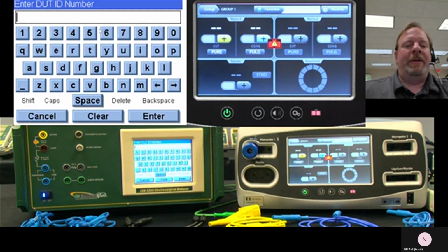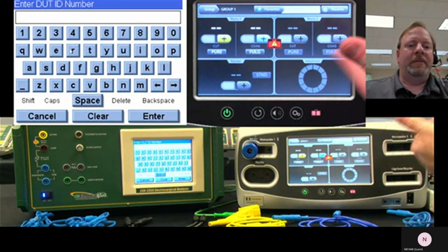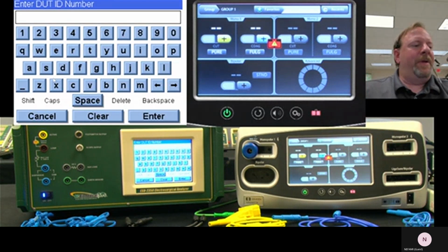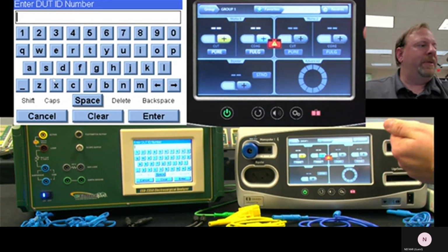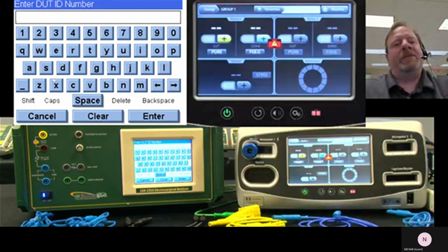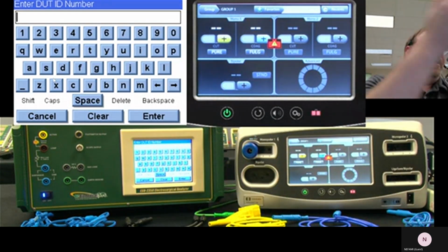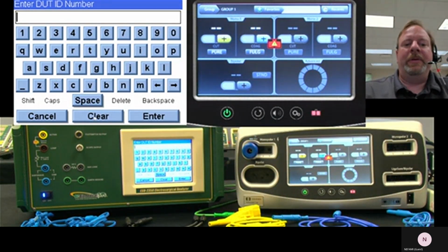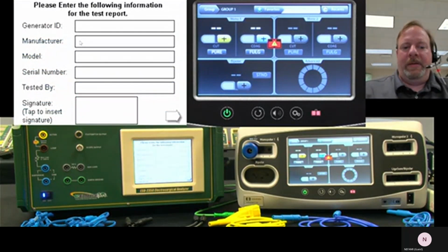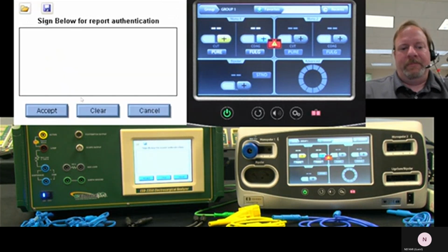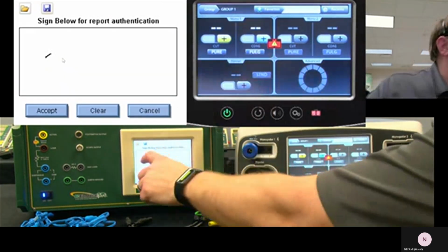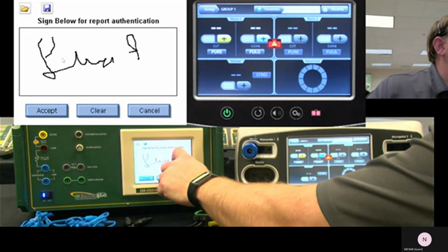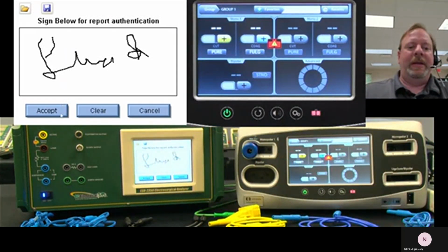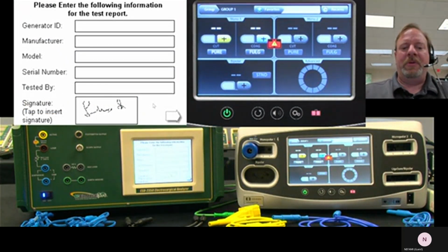And now we can enter information about our device under test. So if we have a barcode scanner, we can plug that into the USB port on the side of the 2350, and I can scan my barcode that's got my ID number, manufacturer information, model, all that can be in there. Kind of cute thing here. So if we want to sign this, we can do a signature on the screen, and that will then be saved into my report. Just proof of who did the testing.